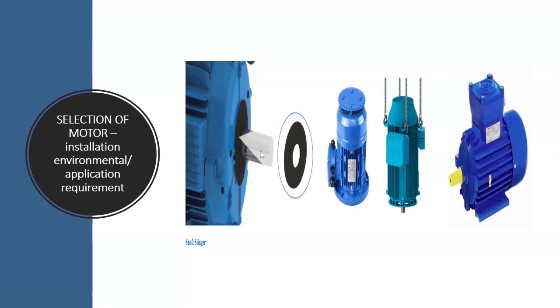I remember during my early days in my career, we had a flotation plant where general purpose motor was used for the vertically mounted motors. You install a bearing and within 3 months, you have to replace. And basically, after a motor has undergone overhauling, we don't subject it to the test to ensure that the right IP rating is in place. So it's better you procure a motor with a shaft slinger to protect it against the ingress of chemicals, slurry, and rain on the shaft because it is vertically mounted.